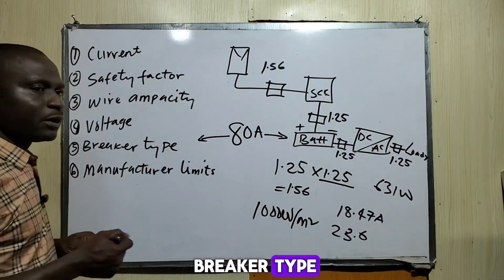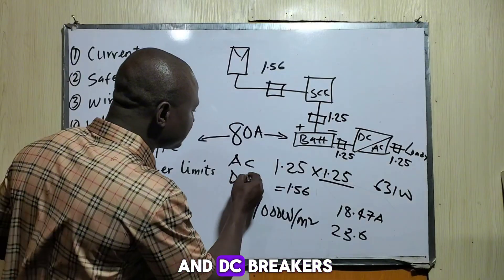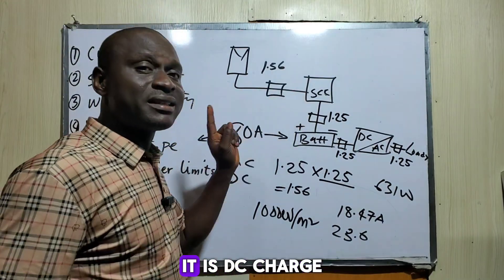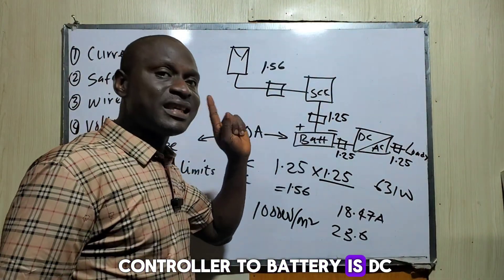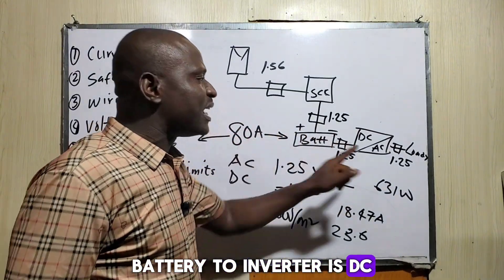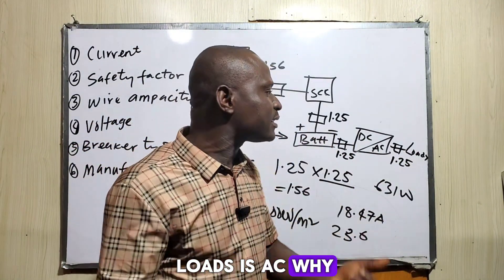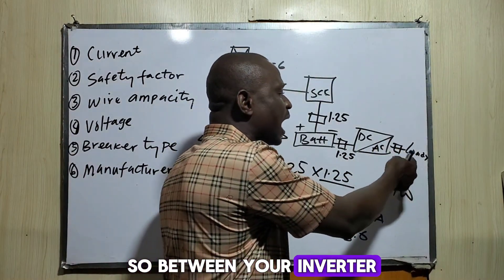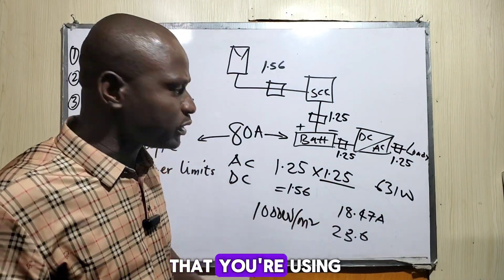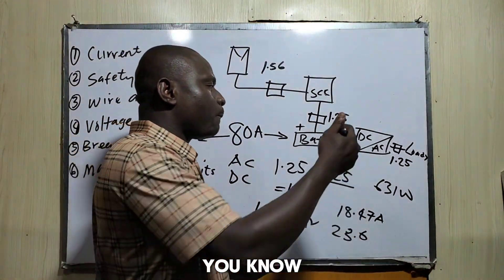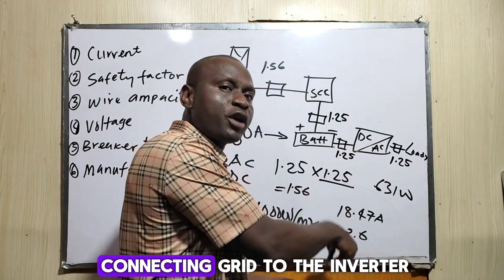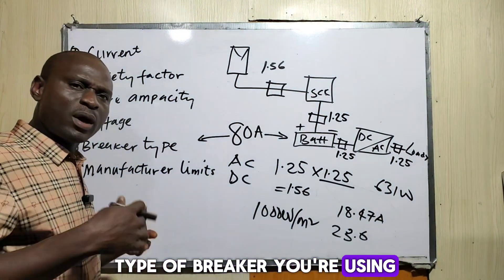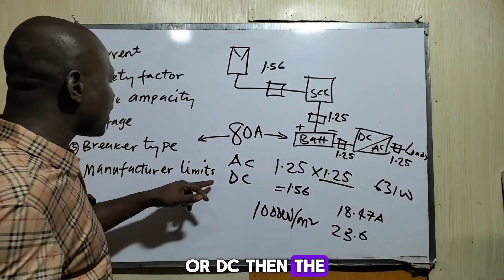Then we have the breaker type — AC breakers and DC breakers. From solar panel to charge controller is DC; charge controller to battery is DC; battery to inverter is DC. Then inverter to your load is AC, because the inverter has converted DC to AC. Between your inverter output and your load, use an AC breaker. If you are connecting the grid to the inverter, you also use AC.